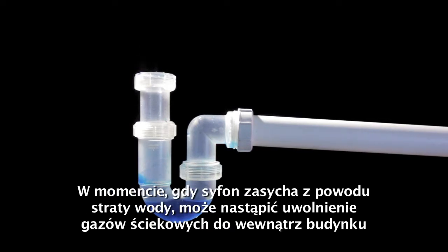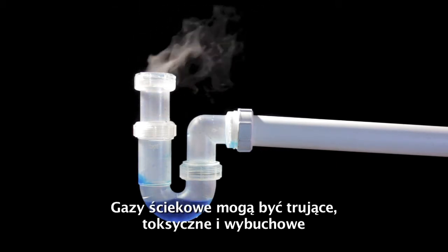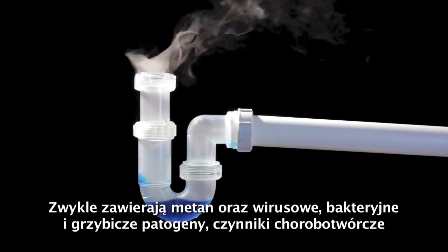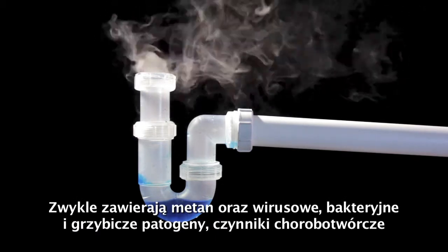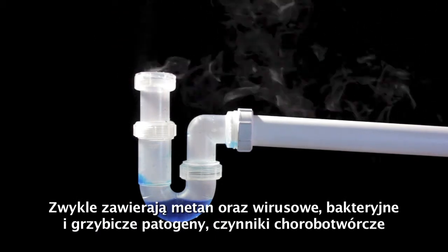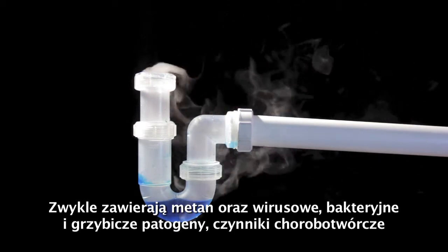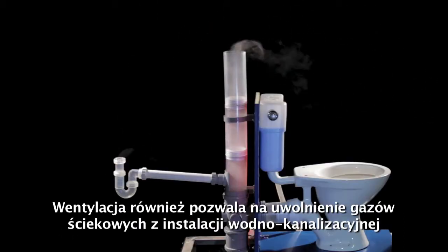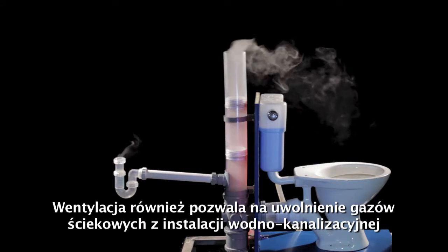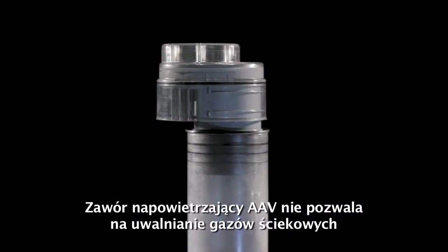Where a trap has lost the water seal, this conduit can allow sewer gases to enter the building. Sewer gases can be noxious, toxic, and explosive. They normally contain methane and may potentially contain viral, bacterial, and fungal pathogens in addition to other organisms. Ventilation also allows sewer gases to escape the plumbing system. An AAV will not allow sewer gas to escape.